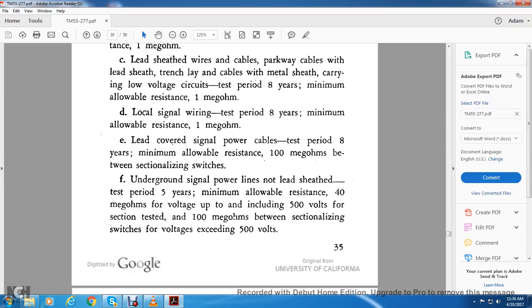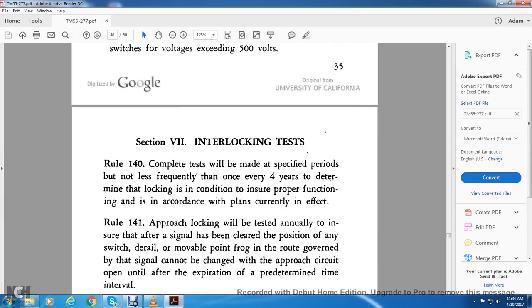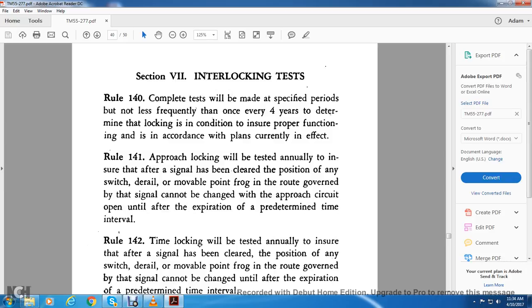F. Underground signal power lines not sheathed: test period of 5 years, minimum allowable resistance 40 megohms for voltage up to and including 500 volts for sections tested, and 100 megohms between sectionalizing switches for voltage exceeding 500 volts.